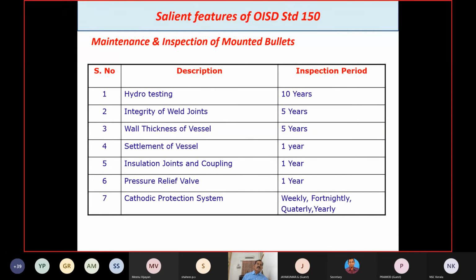Maintenance inspection of mounded bullets: these bullets should be hydrotested once in 10 years, and NDT should be carried out once in 5 years. We have to decommission the bullet, and people will go inside and do the non-destructive testing to check the integrity of weld joints and wall thickness of the vessel, and that will be done once every 5 years. The settlement of the vessel will be checked every year, and the insulation joints and couplings for cathodic protection will be checked every year. The pressure relief valve, that is the safety relief valve, should be checked every year, and records should be maintained. The cathodic protection system is to be checked weekly, fortnightly, quarterly and yearly. The standard also explains the cathodic protection system and testing methods, everything.